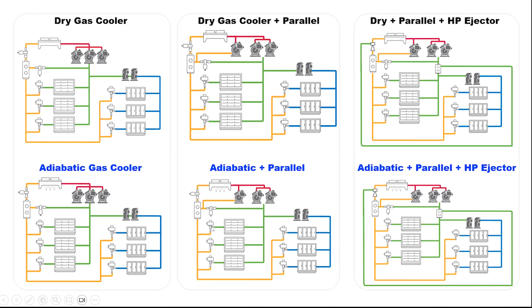And then the OEMs look at it and say, okay, well, I could downsize this compressor, my parallel compressor, to give me the same capacity as these medium temp compressors because I'm operating at 100 PSI higher. So those are the net advantages of wanting a parallel compressor digesting that excessive flash gas from the flash tank in the summer.